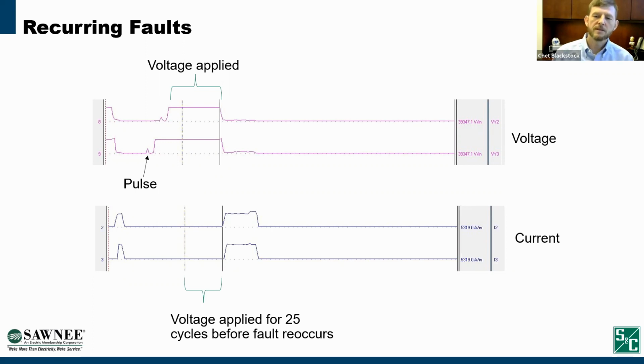That same event is represented by the current below, and on the current chart, you can see where you had zero current. When the contacts closed, because of the scale on this, you can't tell the difference between load current and zero current, but the current stays zero or at load current for 25 cycles after the voltage is applied. So that means that that limb was laying on the line or between these two phases for 25 cycles energized before the fault finally erupted and caused the interrupter to trip back.